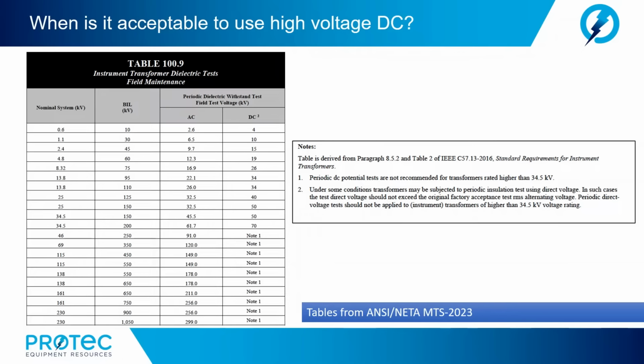Now, under some conditions, transformers may be subjected to periodic insulation tests using direct voltage. In such cases, the test direct voltage should not exceed the original factory acceptance test RMS alternating voltage. Periodic DC voltage tests should not be applied to instrument transformers of higher than 34.5 kV voltage rating. So again, we do see that there are limitations to where we can use high voltage DC.